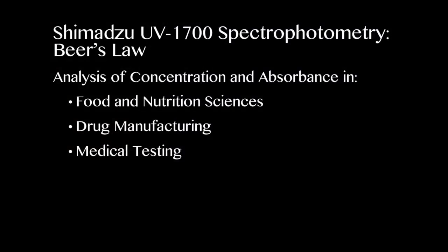The UV-1700 is used to analyze the relationship between concentration and absorbance as shown in Beer's Law, which has popular applications to food, drug, and medical testing.